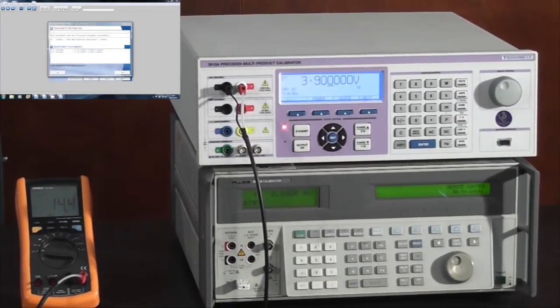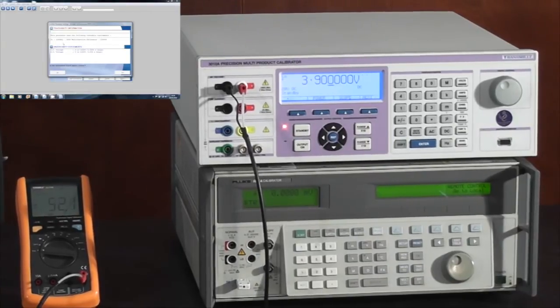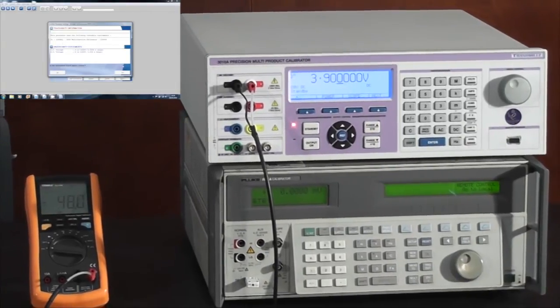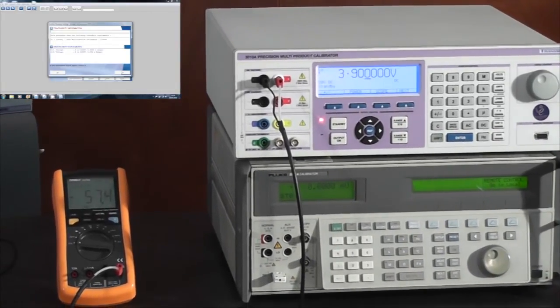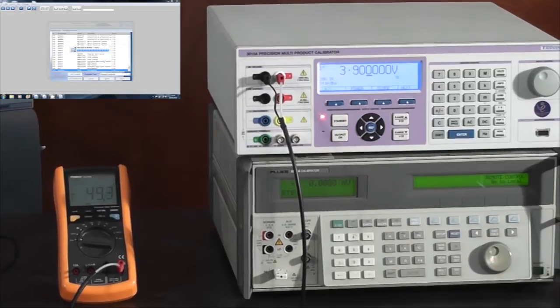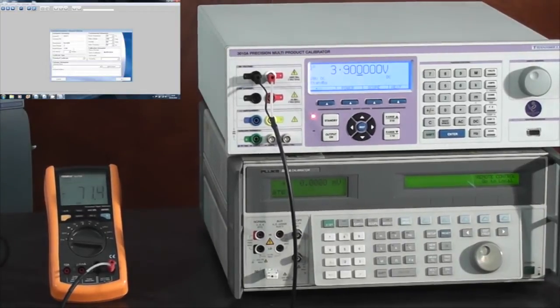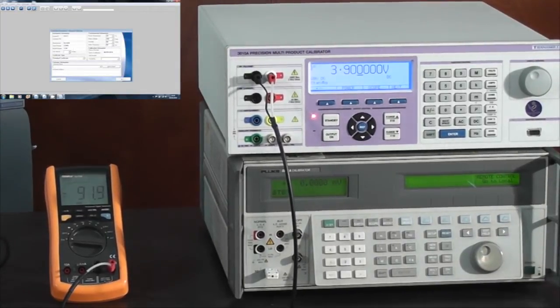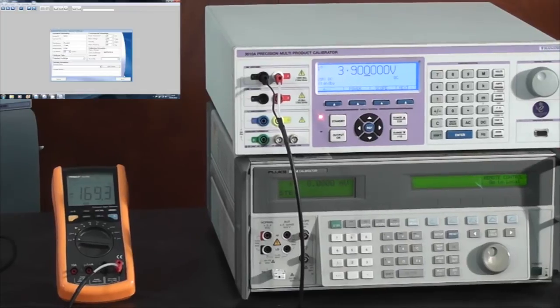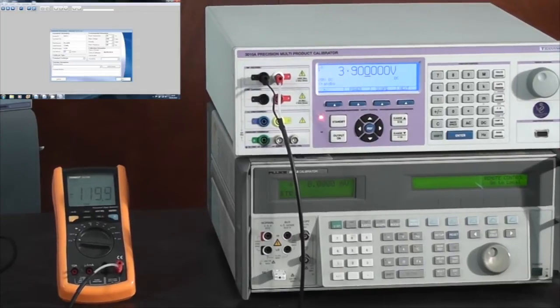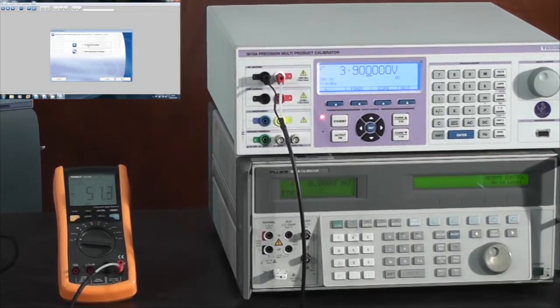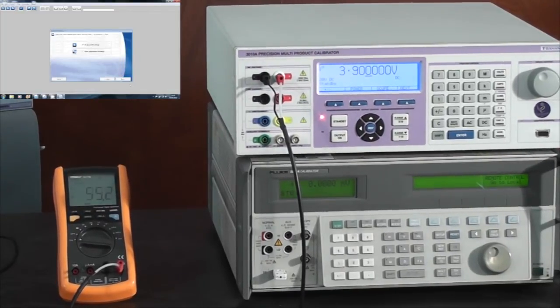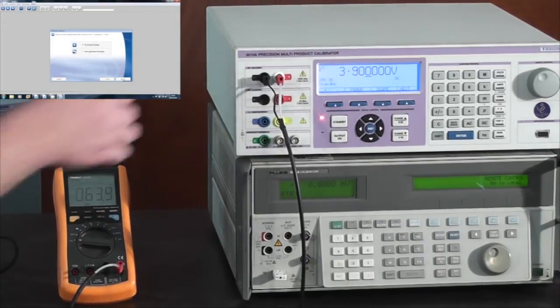Now we see in the traceability it's displaying the 5500 instead of the 3010. Enter a serial number and a calibration interval, select as found readings, and once again we are now going to start the calibration.